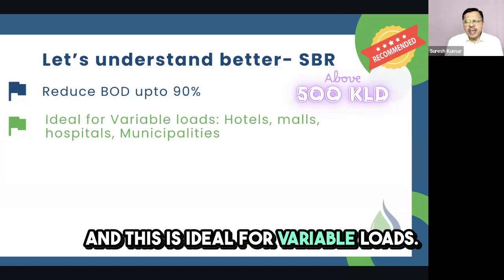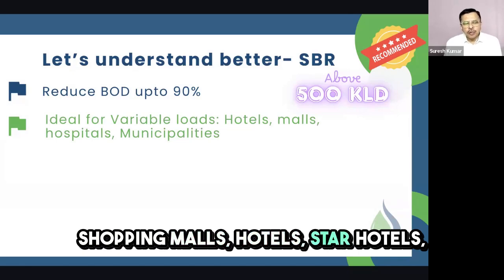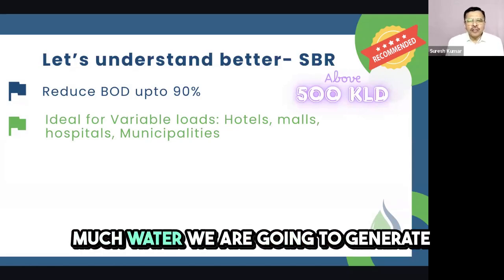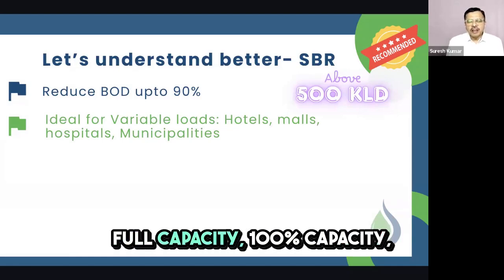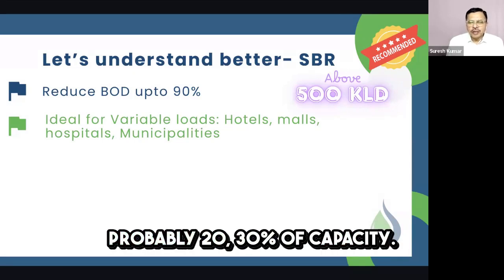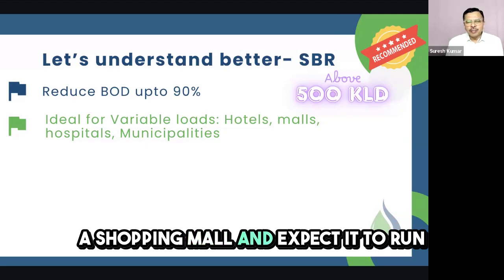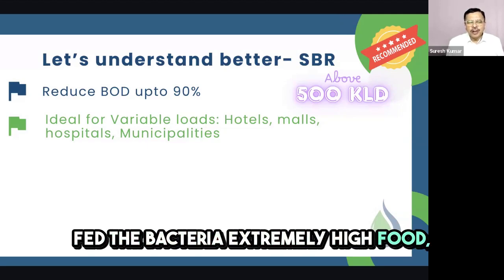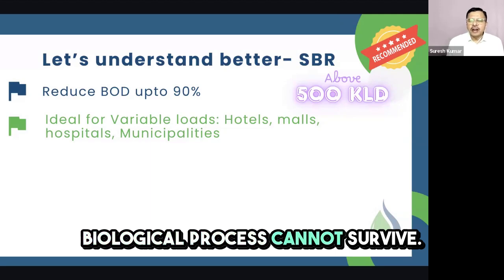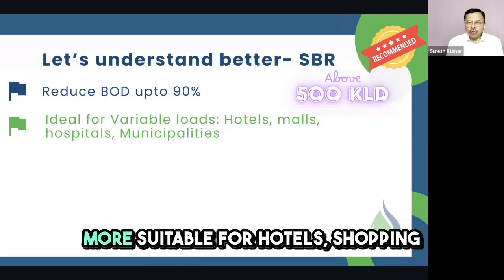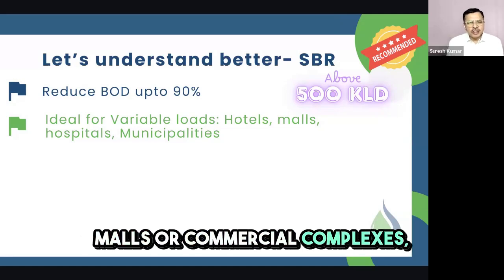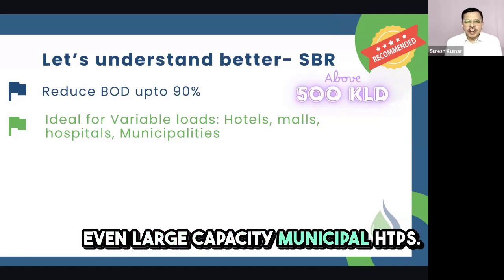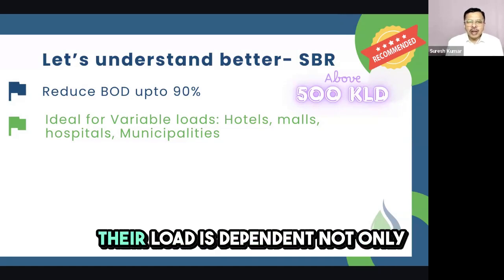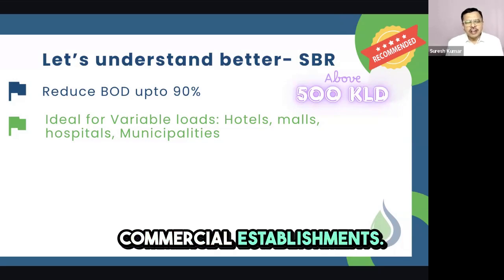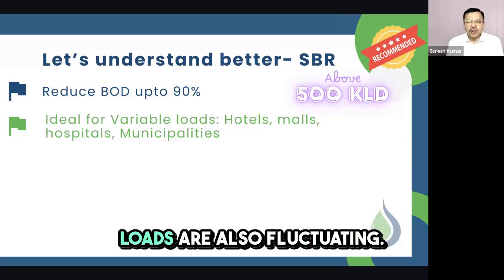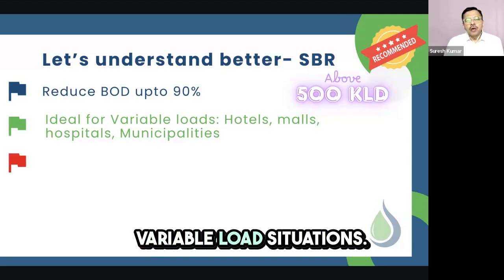SBR is ideal for variable loads. In places like shopping malls, star hotels, hospitals, and even municipalities, we don't know exactly how much water will be generated. In a shopping mall, weekends may see 100% capacity while other days it may be only 20-30%. You can't set up an MBBR in a shopping mall and expect it to run properly, because one day the bacteria get extremely high food and the next day there's none — biological processes can't survive that. So SBR is more suitable for hotels, shopping malls, commercial complexes, IT buildings, hospitals, or even large capacity municipal STPs, since municipal loads also fluctuate depending on commercial establishments.